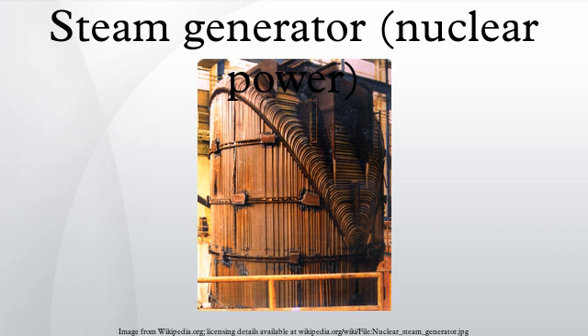Westinghouse and Combustion Engineering designs have vertical U-tubes with inverted tubes for the primary water. Canadian, Japanese, French, and German PWR suppliers use the vertical configuration as well. Russian VVER reactor designs use horizontal steam generators, which have the tubes mounted horizontally. Babcock and Wilcox plants have smaller steam generators that force water through the top of the OTSGs and out the bottom to be recirculated by the reactor coolant pumps. The horizontal design has proven to be less susceptible to degradation than the vertical U-tube design.